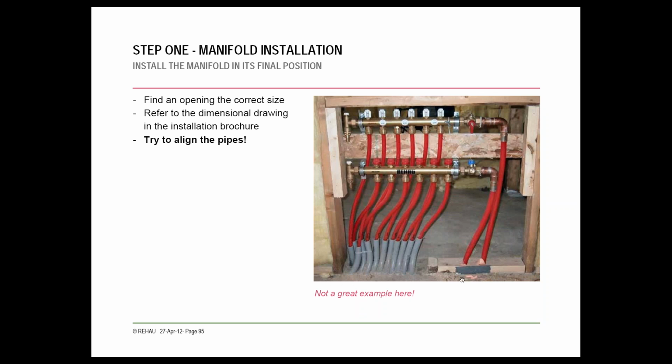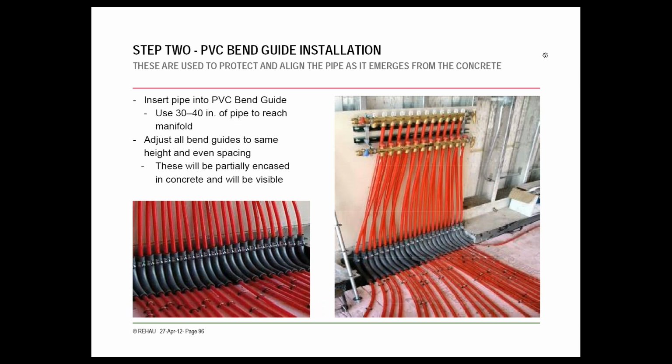Here they're pointing out that this isn't the greatest example because it's not lined up properly, but this is still a pretty decent manifold installation. They've routed them all up through the flooring, and they are bunched to the left a little bit, but depending on what's existing, you might not always have other options. Ideally, yes, you do want to have them all nicely lined up. The better your manifold station looks, the more professional the job looks, of course.